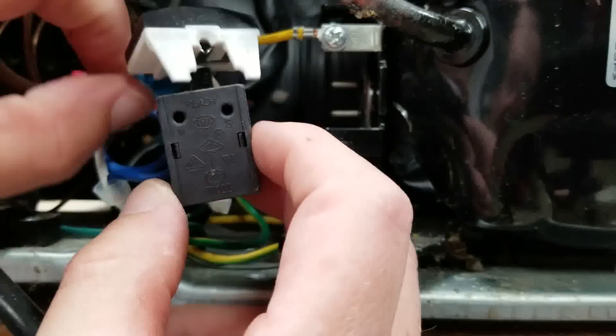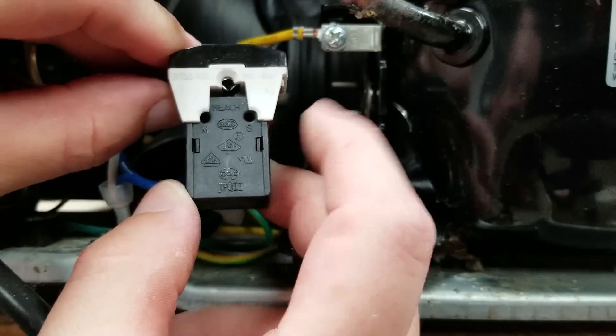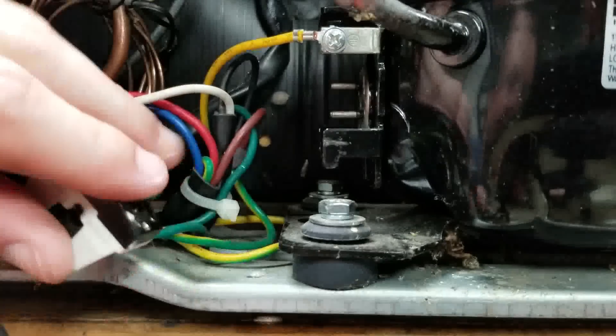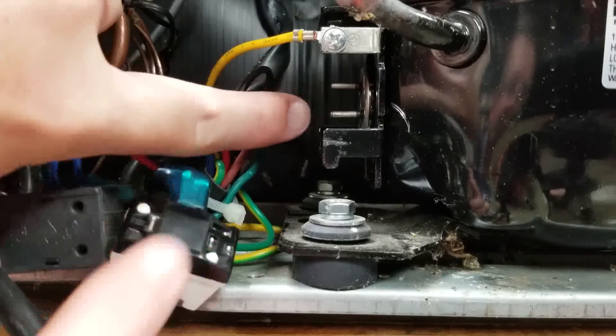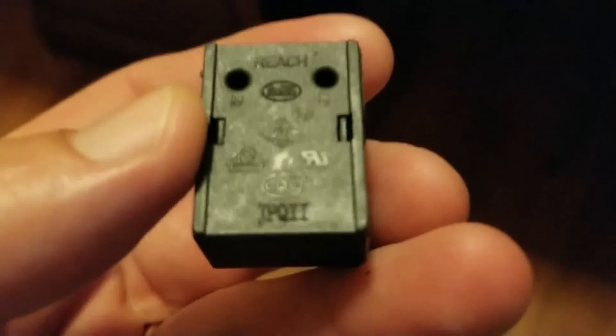This was situated in here like this, and these three pins are what connect to the compressor — you see the three pins right here. That's pretty typical on these little small compressors; that's how they hook up. So this is that little starter piece I took off of that compressor.